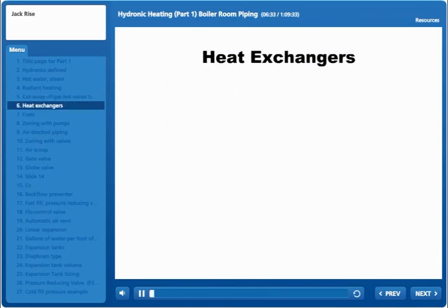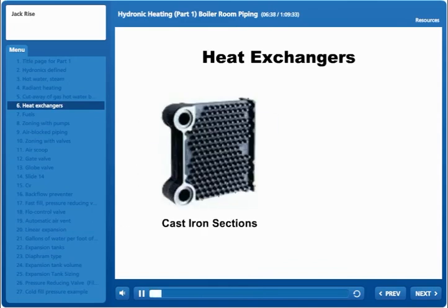Let's take a look at some of the stuff we just looked at in the last slide. And the heat exchanger is most of the boiler. It takes up the greatest amount of room and certainly does a lot of the work. Now you see the big opening in the bottom left. That's where the cold water enters. The cold water is heated up and then discharges out the top. Okay, hot water rises. So the cold water enters. These sections are put together by push nipples. I'm going to show you a picture of that in a few slides.